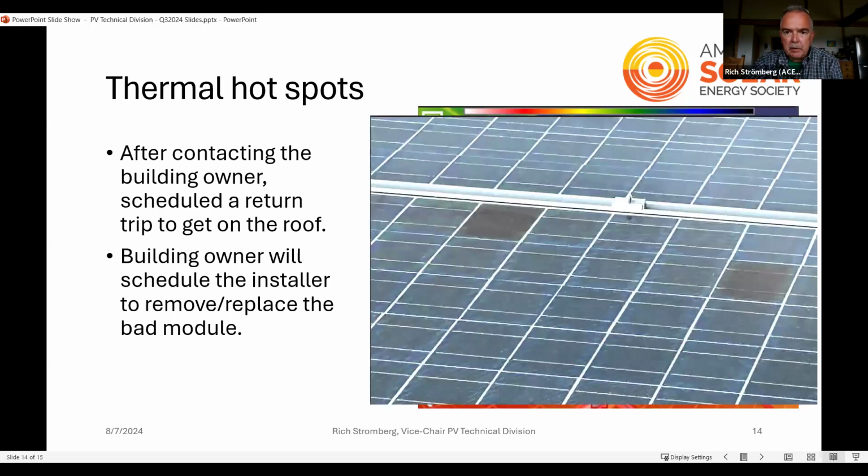And then I had my visible wavelength camera with an optical zoom that's quite good, and you could see that the encapsulant on each of those cells had discolored at a much greater rate. You can see these other cells have some discoloration of the encapsulant, but it's very uniform.